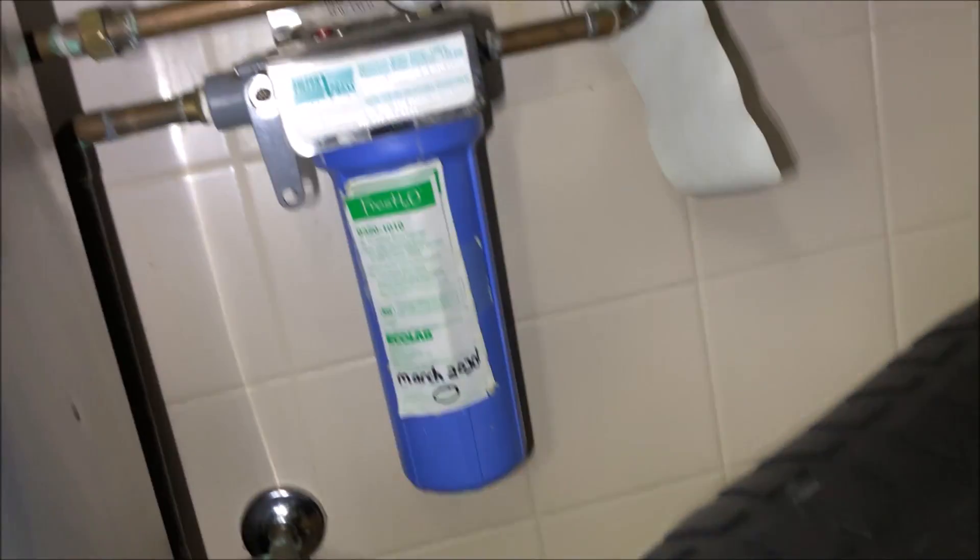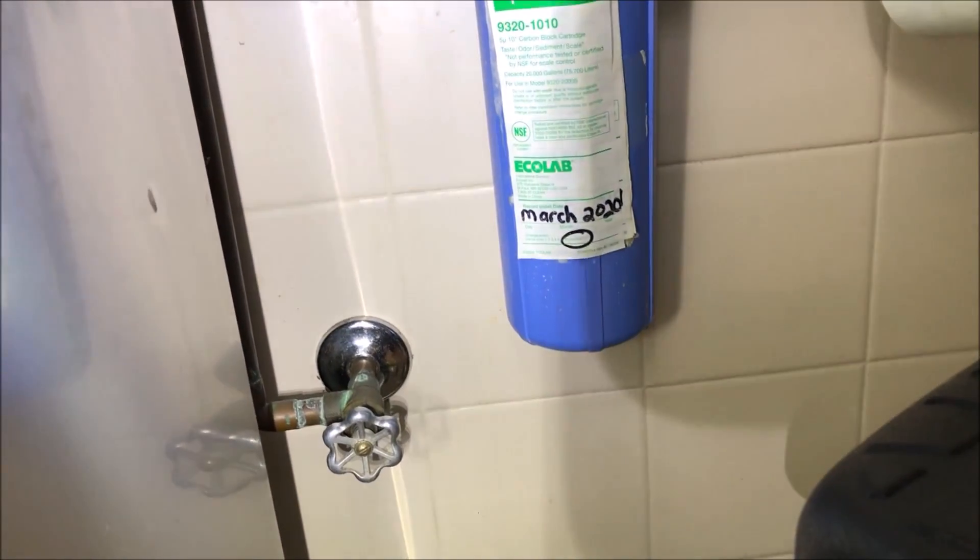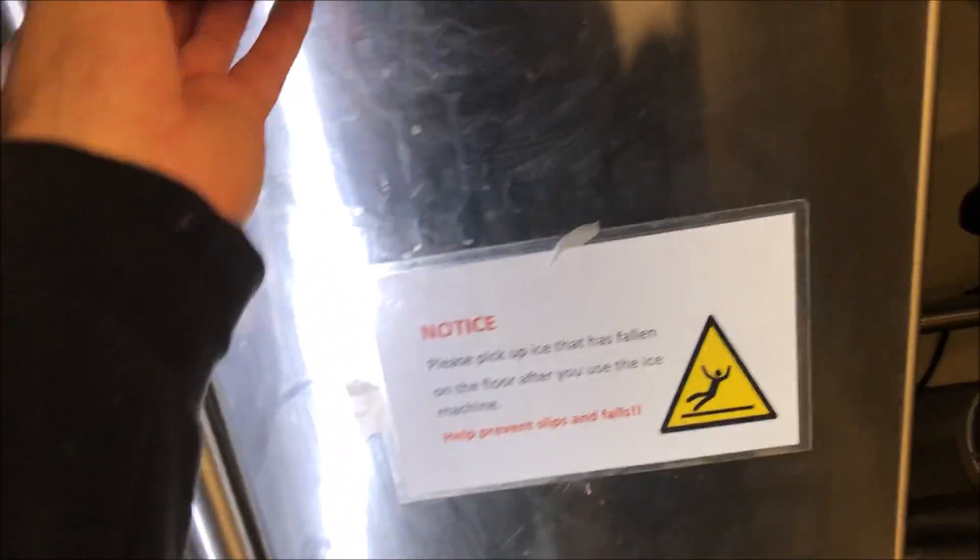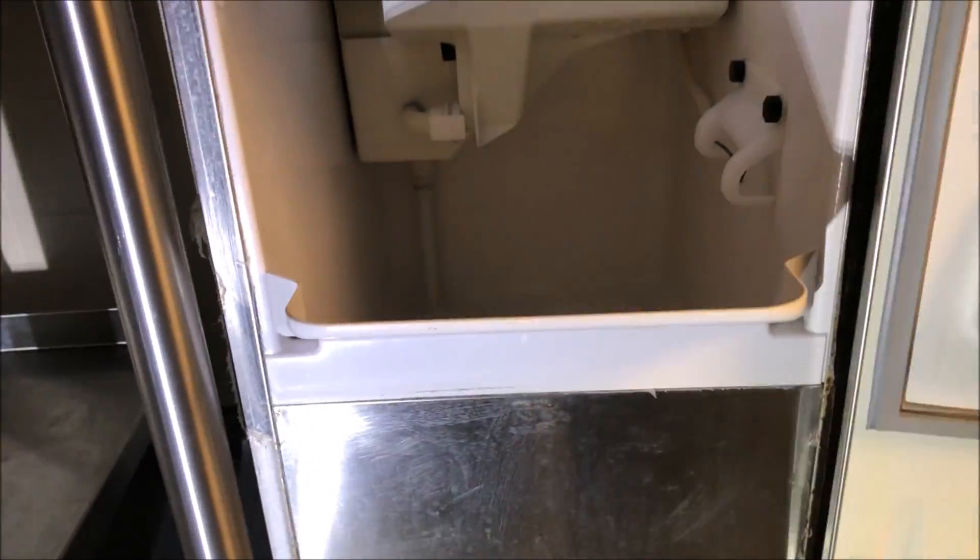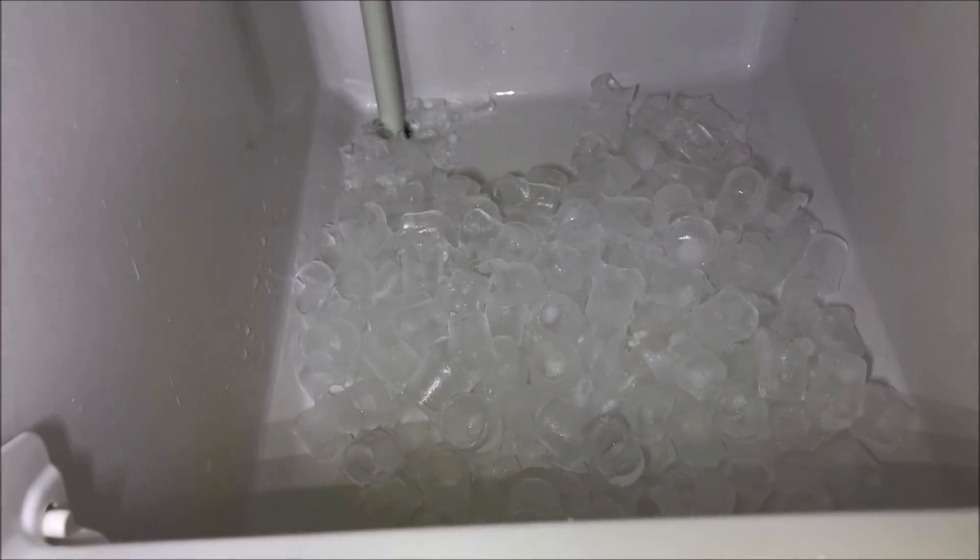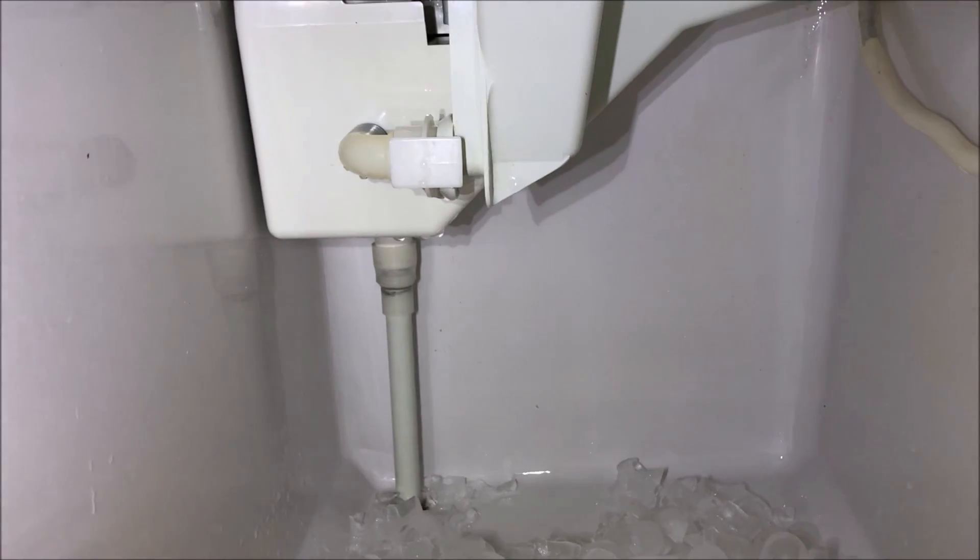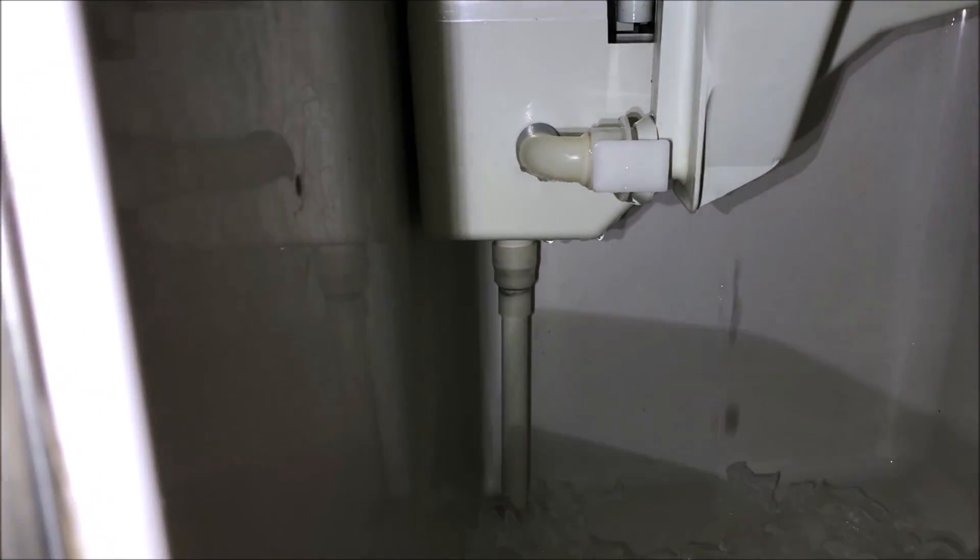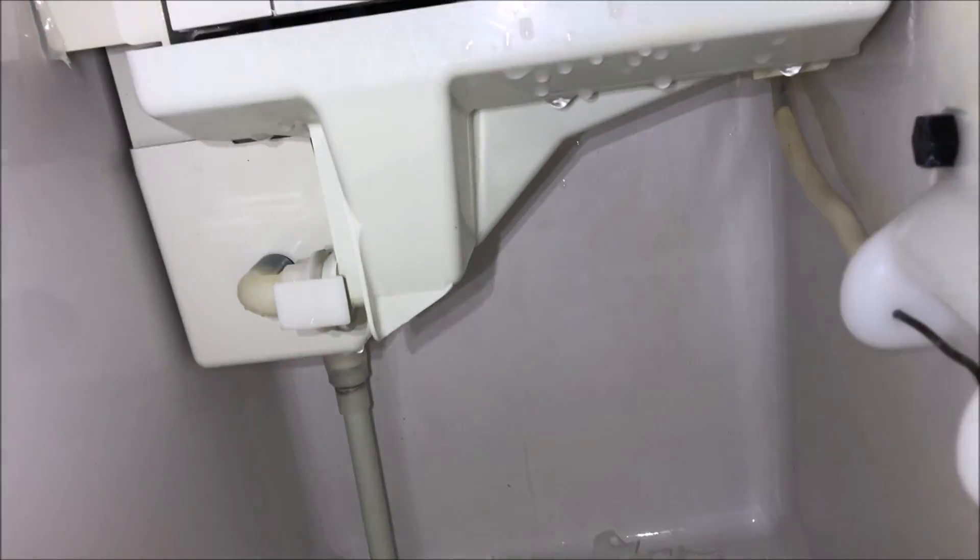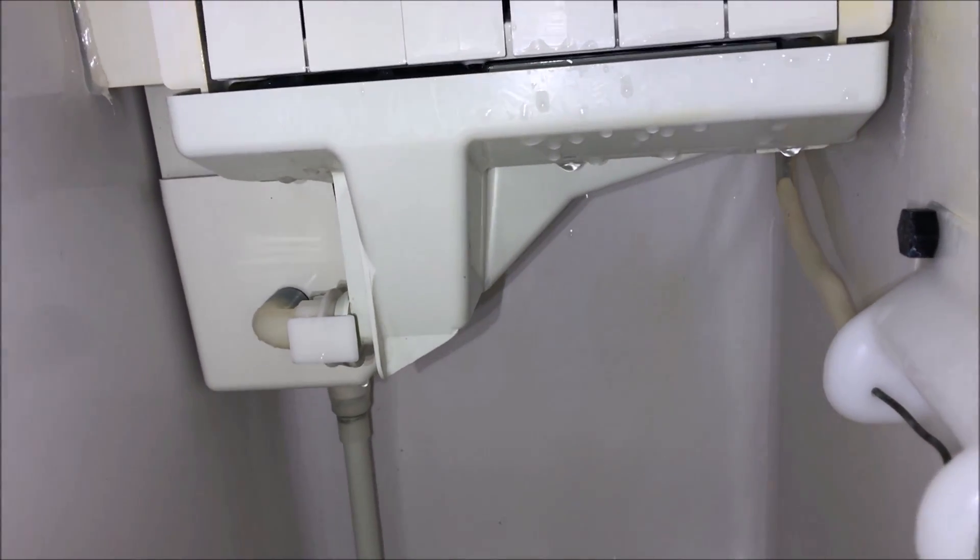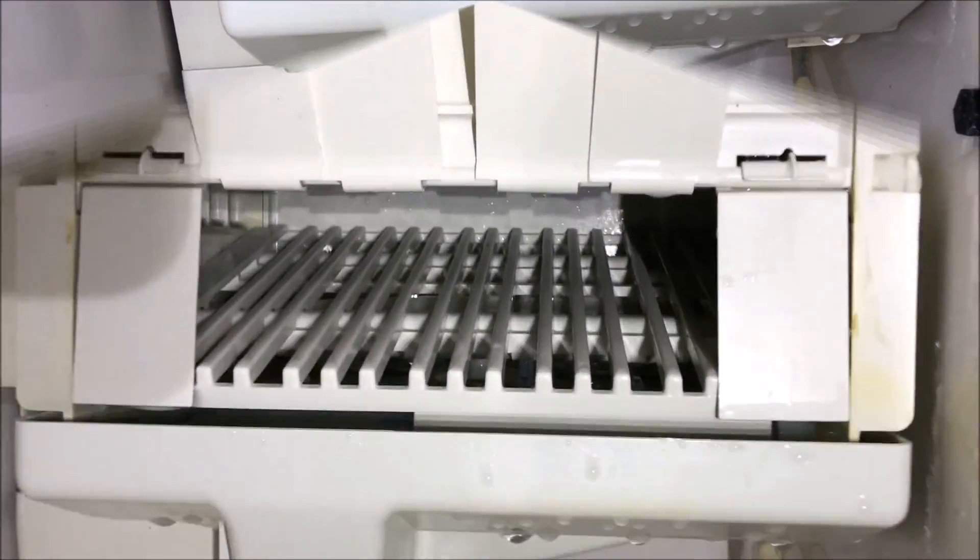First thing I want to make sure water's on. Filters are two years old so that's definitely a concern there. Let's take a peek in here. We've got a little bit of ice, some dripping. But they said they've been running this for like two days. Definitely not enough ice in that bin.